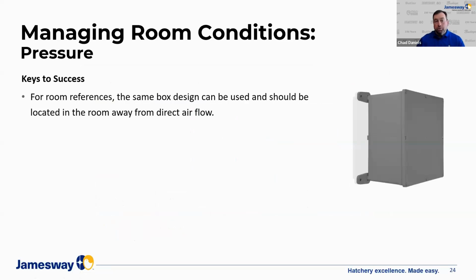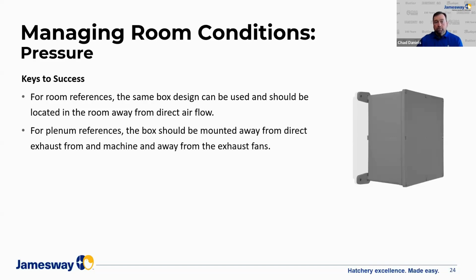In addition to that, for room references, that same box design can be used, but you need to make sure you locate it in the room and away from direct airflow, like from a rooftop unit or from a supply fresh air or recirculation fan that's mounted in the room. Just make sure the box is away from that. For plenum references, the box should be mounted away from direct exhaust from a machine.